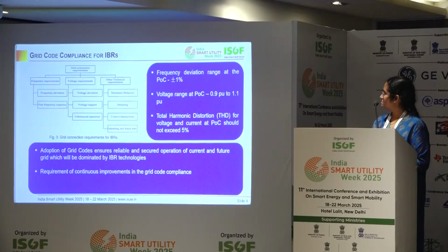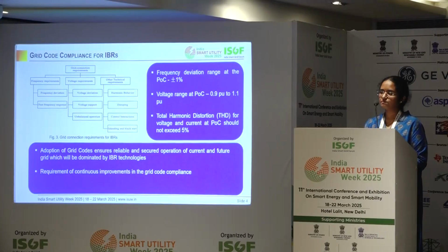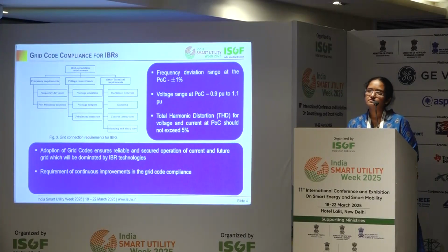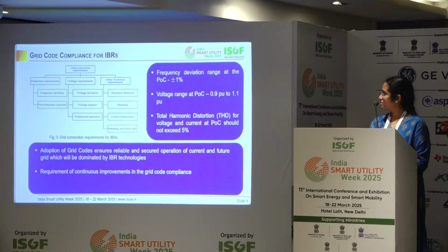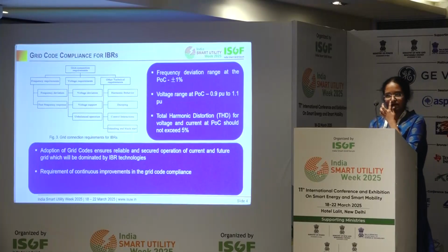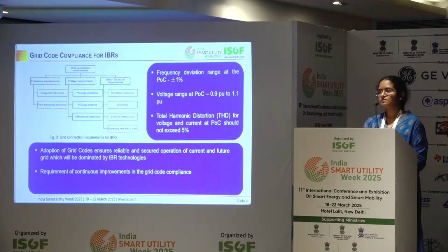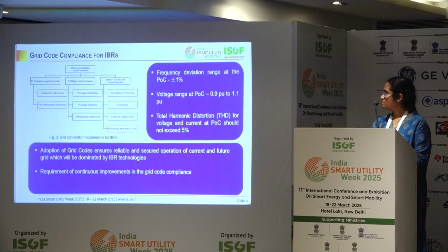Here, if you see, according to the grid code, frequency deviation must be under plus or minus 1% at the point of coupling, and voltage deviation must be within 0.9 to 1.1 per unit, which means 10% voltage deviation is allowed. The total harmonic distortion should not exceed 5%. Reactive power deviation also must not exceed 5%. All the LVRT designs should be in compliance with the grid codes. We have considered the 2007 CEA grid code for our study.